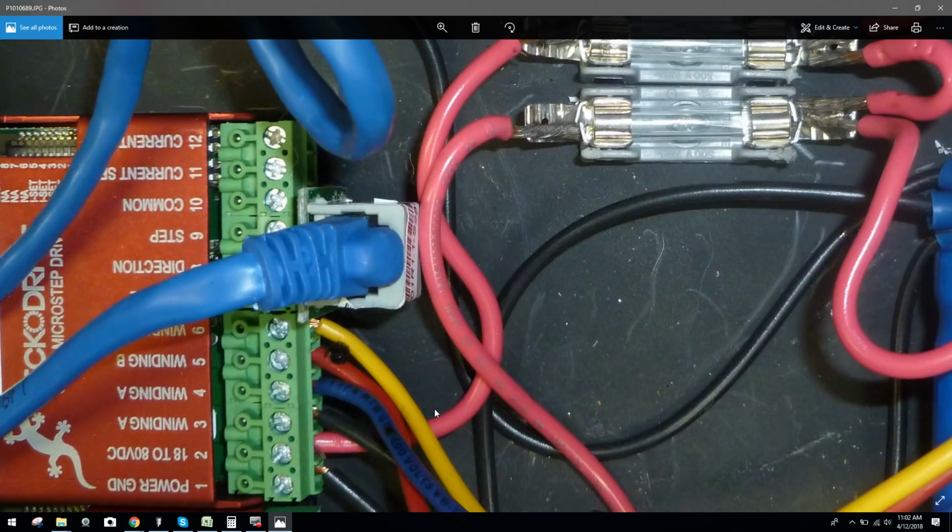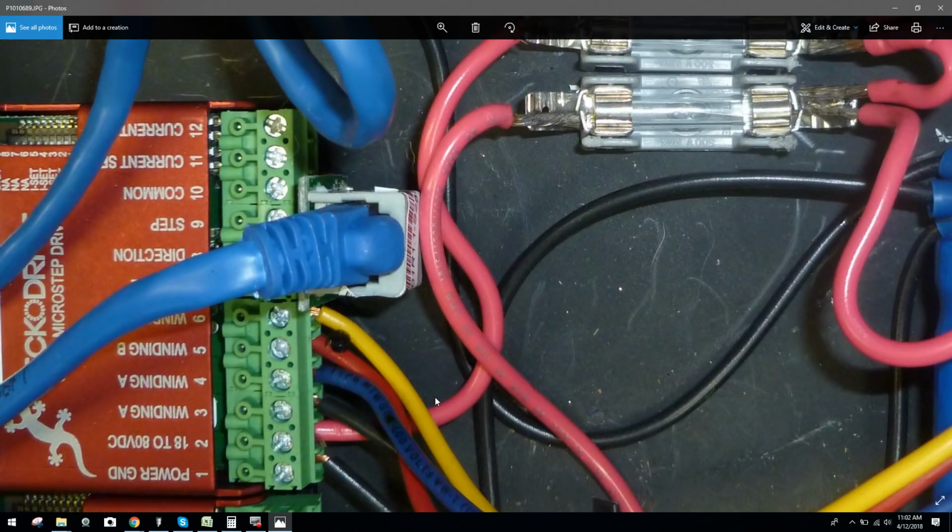That's another thing, guys. I'm going to tell you right now, and this is my own personal opinion, everybody's varies. I like to tin all my leads that are going into an actual terminal block. Now, there are a lot of different methods as far as how that goes. With these terminal blocks that Gecko uses and so many other vendors use, you're not supposed to be using that kind of pressure when you apply a lead inside of it. And you're certainly not servicing the unit on a daily basis where you're removing and going back in.